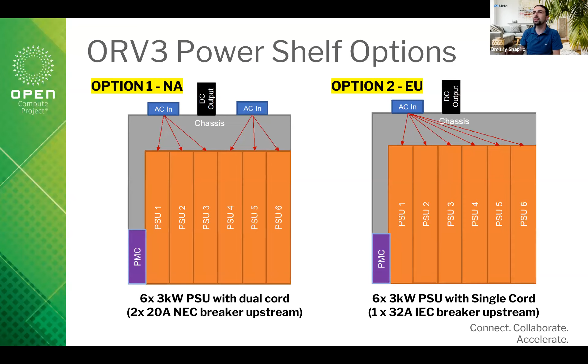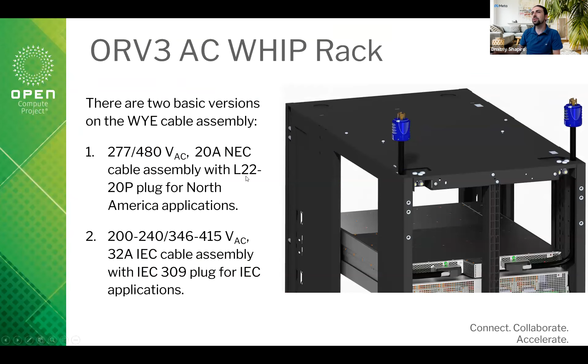Quick overview: North America uses 20 amp at 277/480 volt AC with the L22-20P plugs, shown here, and the EU version uses a 32 amp IEC 309 plug.